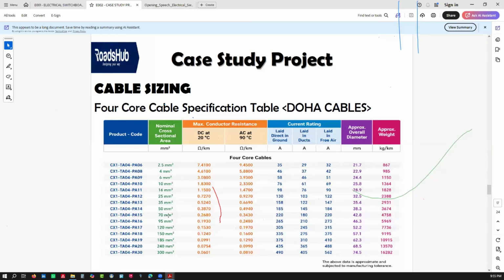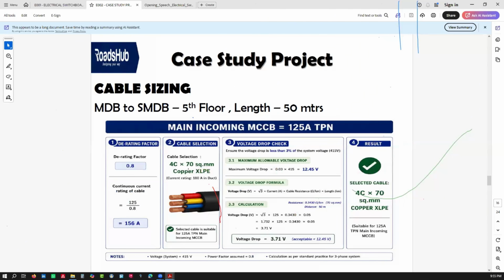Okay, but we also train you on rule of thumbs. So once you get that 70 mm squared cable, it's whatever you've selected, depending on the current that is derated. So you have a 4-core 70 mm copper XLPE cable, and this is how it looks. But now the question you need to ask yourself: how much voltage drop does that cable have? So we now use the voltage drop formula. And I've actually developed these slides so you can understand everything very well.